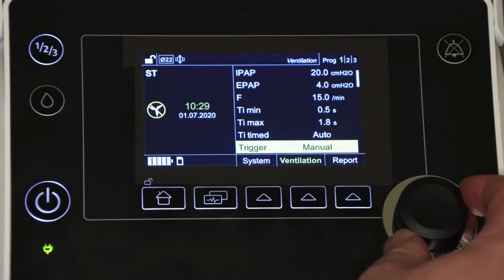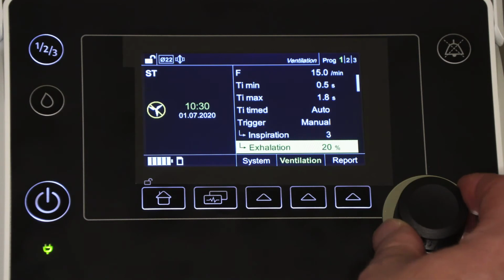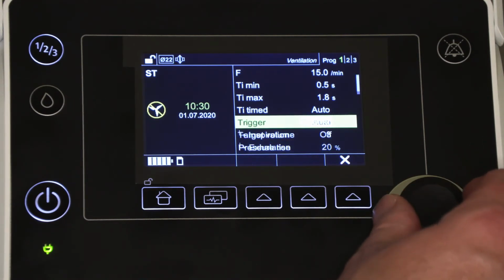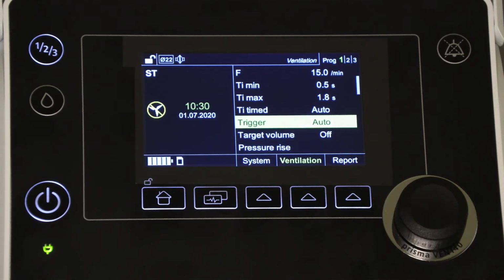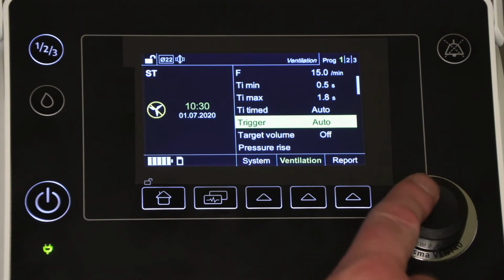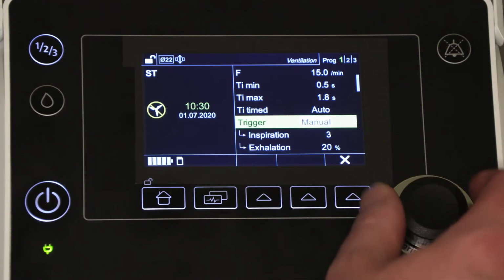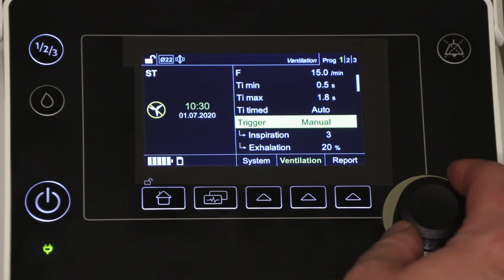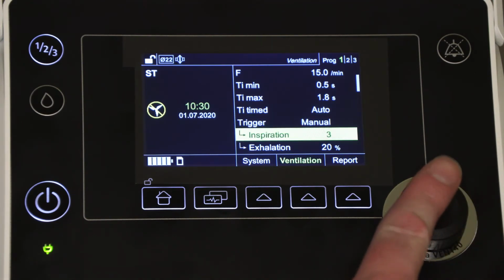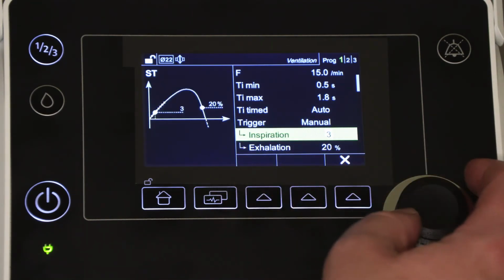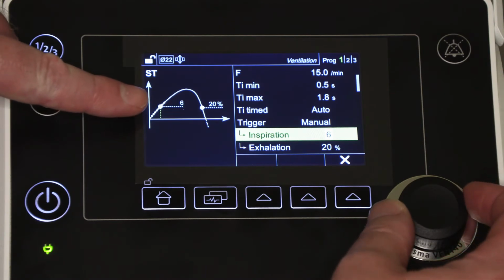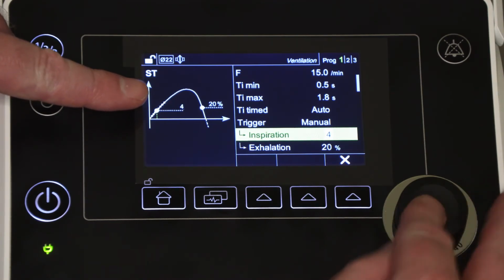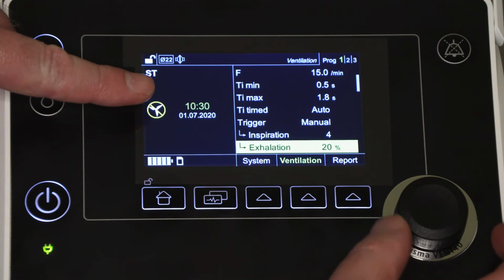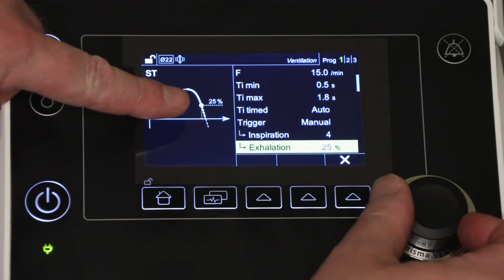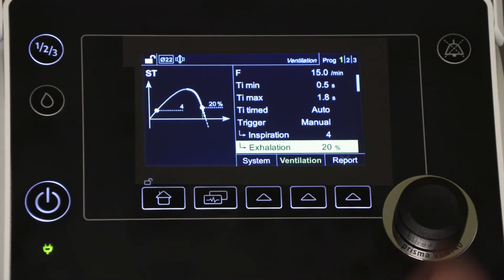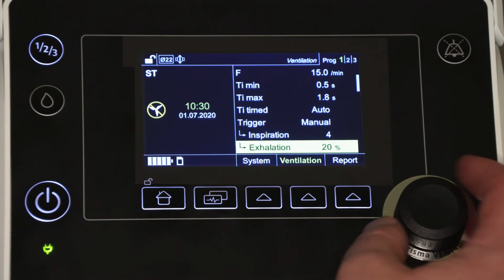The setting for the patient trigger can also be set to auto, as the device has clever algorithms which continuously adjust the trigger sensitivity to meet the patient's requirements. But also this setting can be set to manual for manual adjustment of the patient's triggers. Note that as you apply manual adjustment to these settings, the diagram on the left will show the point of the patient's breath at which either the IPAP or the EPAP will be triggered by the patient.